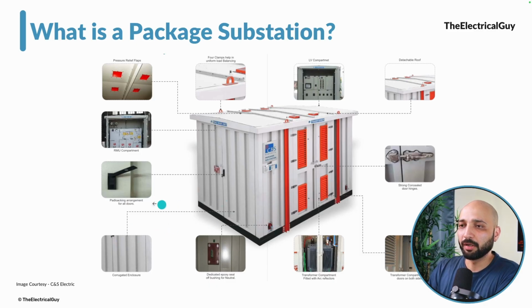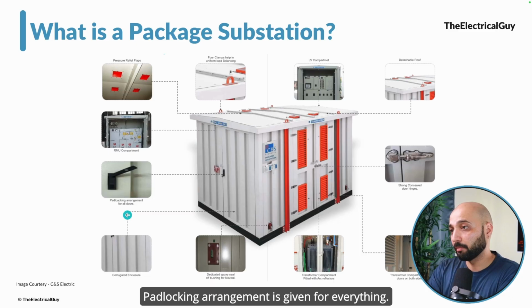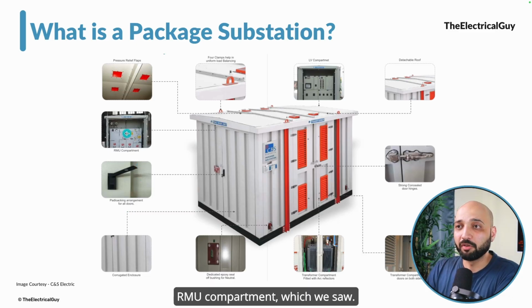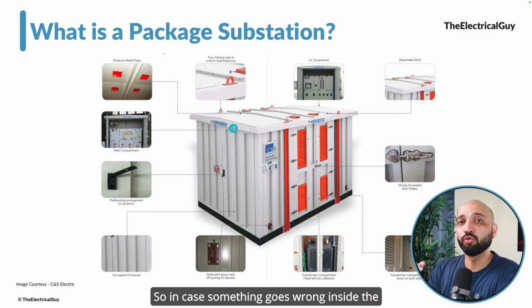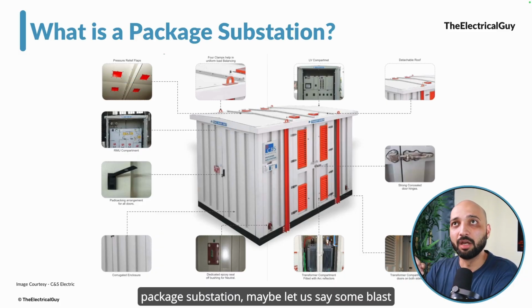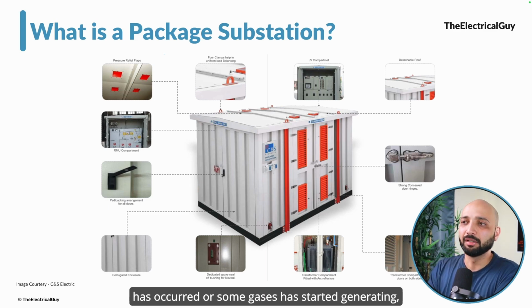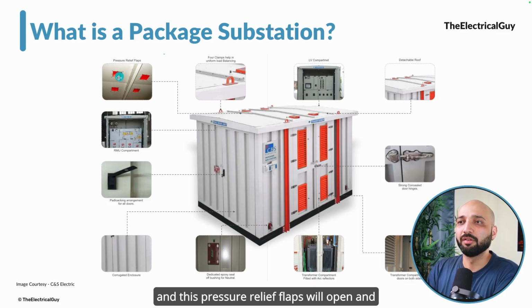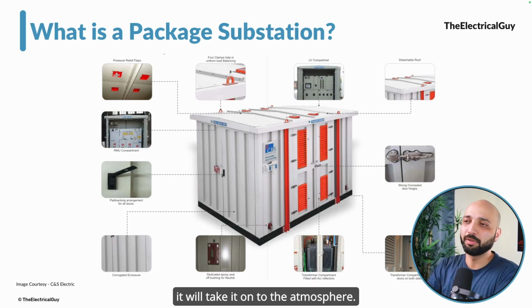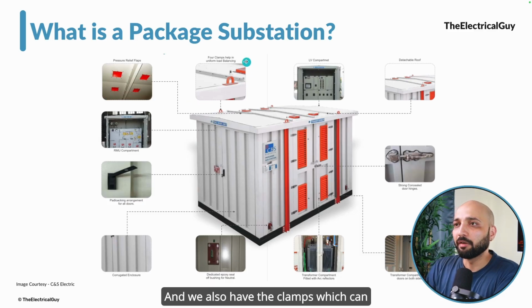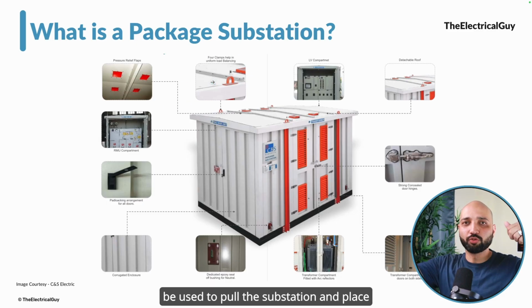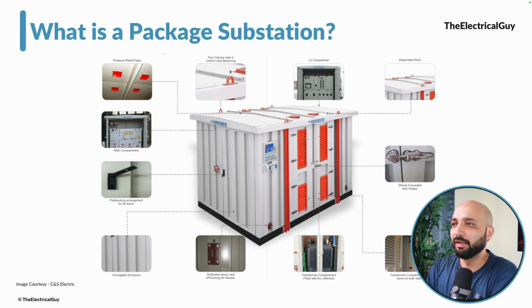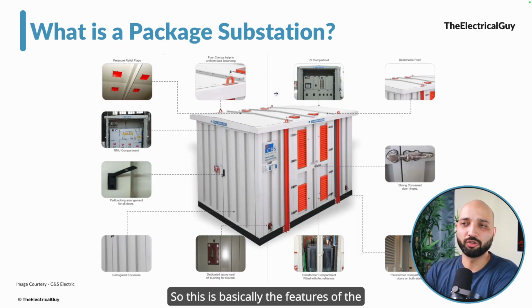This is the enclosure, with a padlocking arrangement given for everything. The RMU compartment which we saw also has a pressure relief flap. In case something goes wrong inside the package substation, maybe a blast occurs or gases start generating, this pressure relief flap will open and release it to the atmosphere. We also have clamps which can be used to pull the substation and place it correctly.